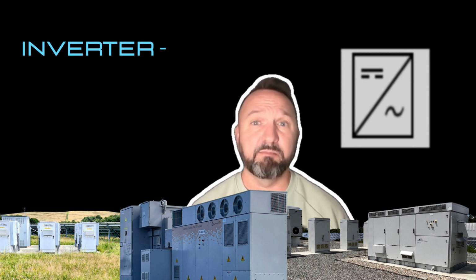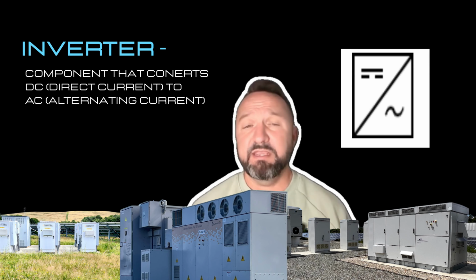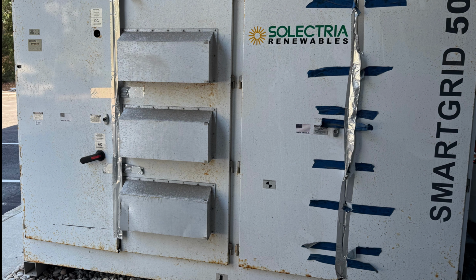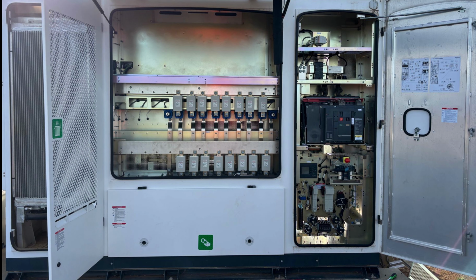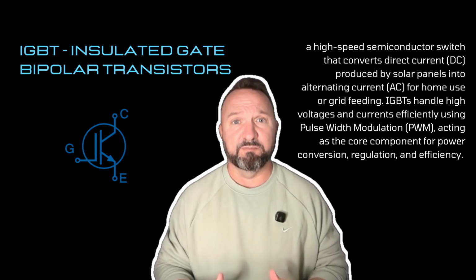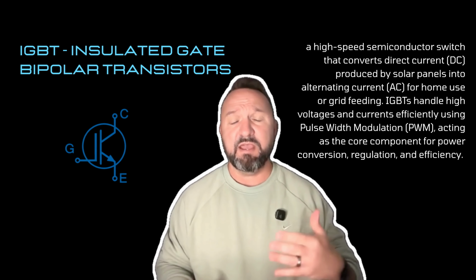So for battery and energy storage sites, inverters are some of the most critical and complex components in the solar site or battery system. They contain the power electronics, the control boards, cooling systems, and protection logic. Now, these components are especially vulnerable to obsolescence because electronics have evolved especially quickly. Common issues are control boards that are no longer manufactured, and cooling fans, assemblies, or cooling parts that are discontinued. So, an entire inverter block may remain offline. One of the biggest failure points is the IGBTs, or the insulated gate bipolar transistors, the main power conversion within the inverter. And if this conversion process can't happen, the inverter simply can't operate and perform its function. That can mean several megawatts of lost production until a solution is identified.